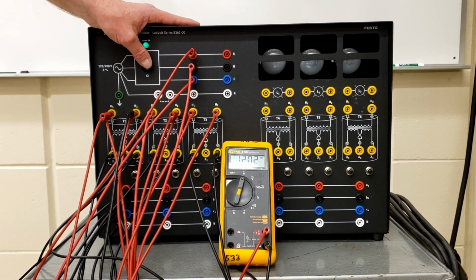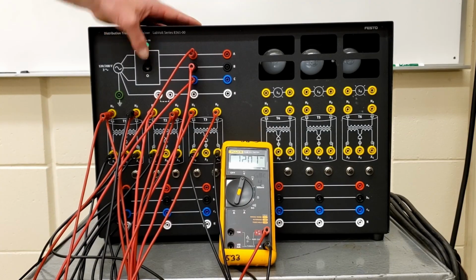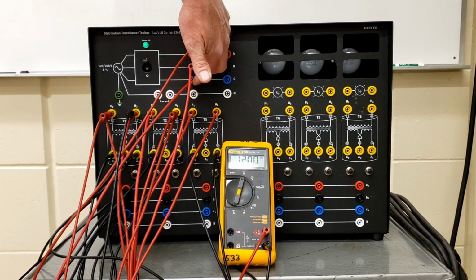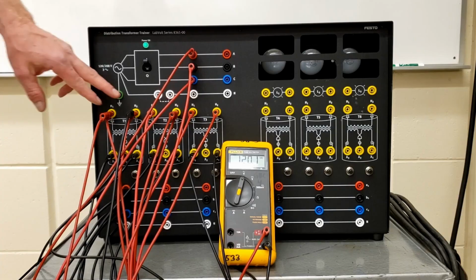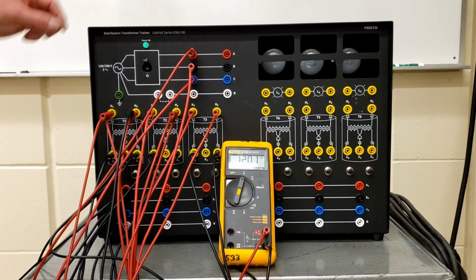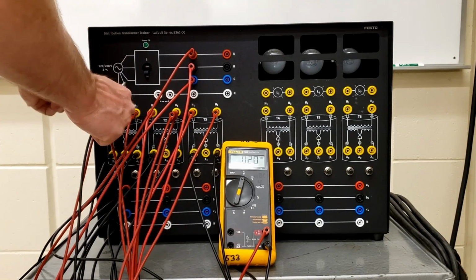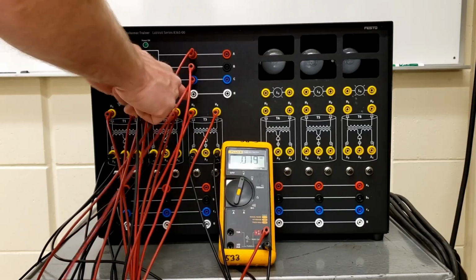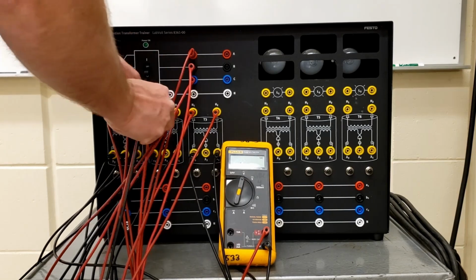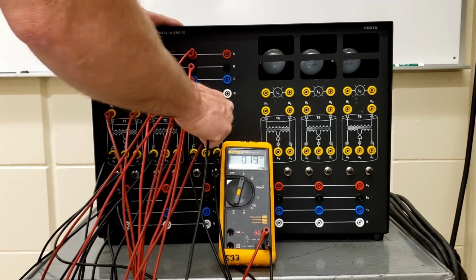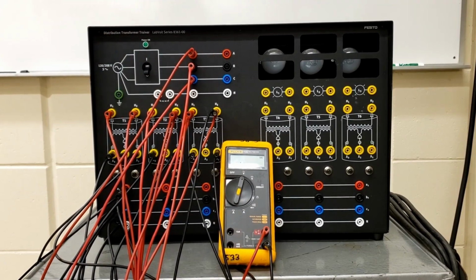Okay, so we have a Y connection now, so we have √3 of our line voltage here. Line voltage was 208. We now have 120 volts on each of the primary windings. You can see here that on our second primary winding, we should have 120 as well. Looks good. And then on our third transformer, we should have 120 volts. Looks good. Okay, so the ratio remains the same between the primary and the secondary.